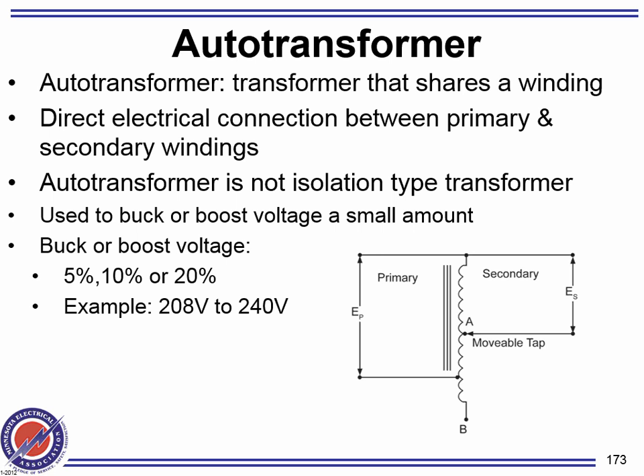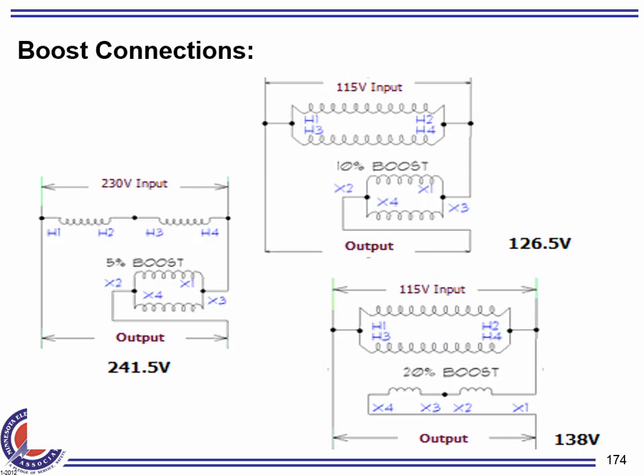So why? Because if equipment is rated for a certain voltage, it wants that voltage. A good example is going from 208 to 240. Remember what happened to the meters that we talked about when it went from 208 to 240, how it added a lot of power on it. It could burn the equipment. Same thing. So we can buck or boost the voltage to match it to the system.